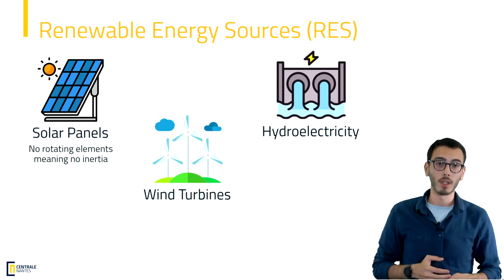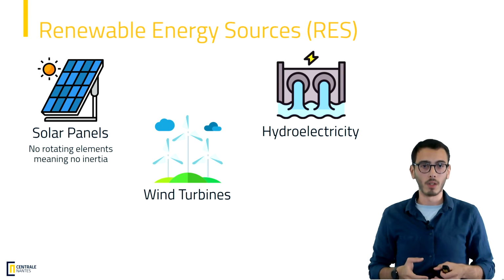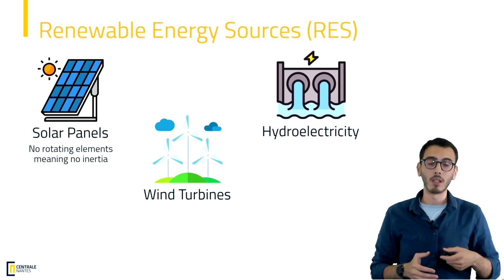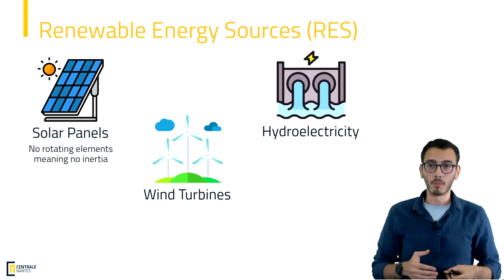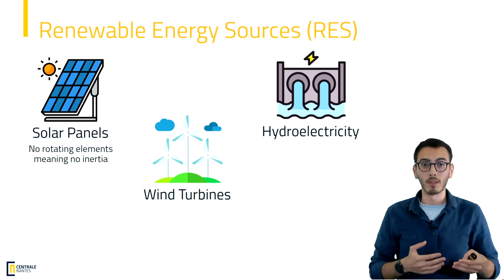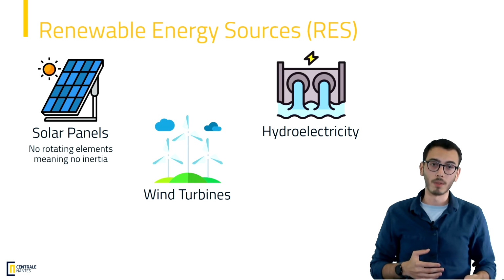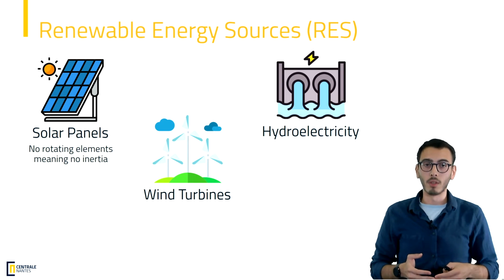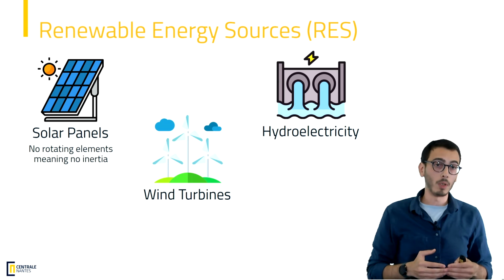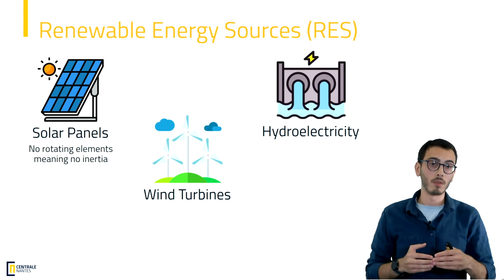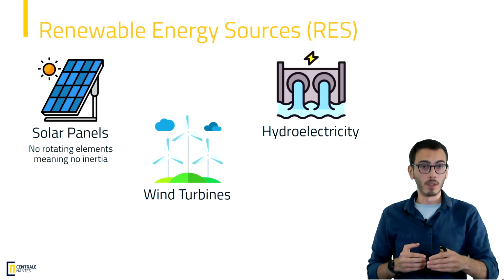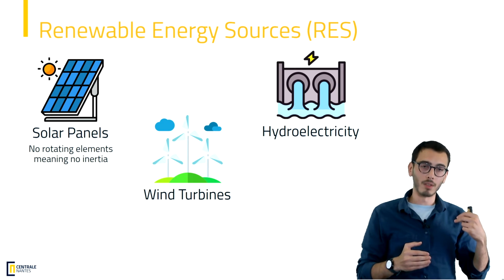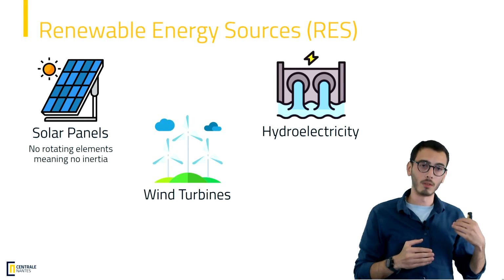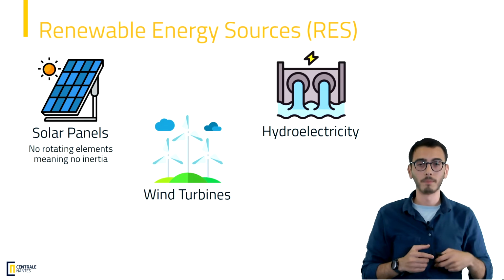So for solar panels, as you may know, solar panels are completely static. They don't have any mechanical parts in them. There are no rotating elements, and thus they do not provide any inertia to the system. On the contrary, they actually take away some of the inertia, because if we increase the renewable energy or the solar power output, that means we have to decrease the diesel engine output, and that means we're reducing the grid stability by reducing inertia.